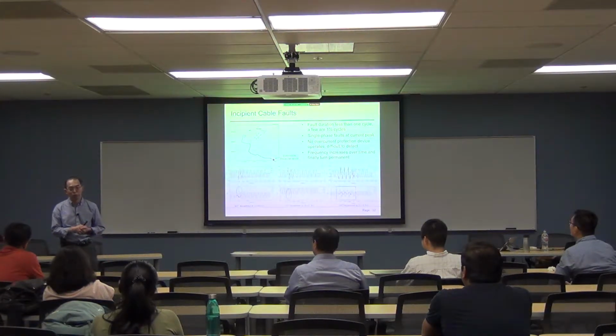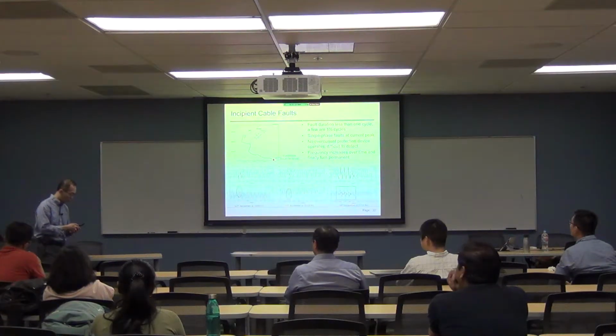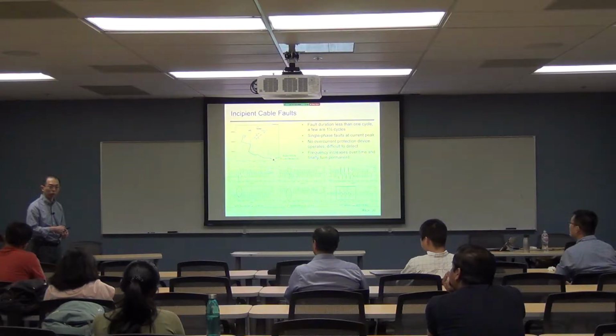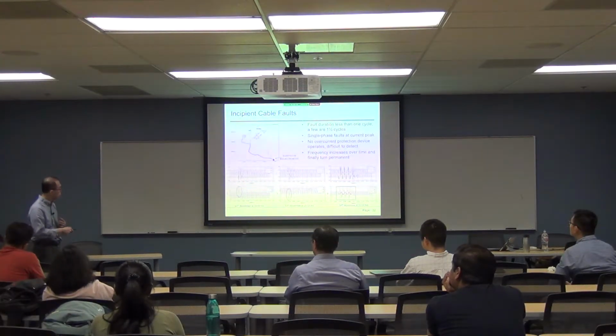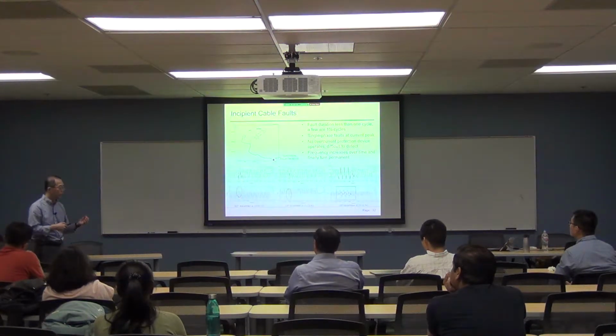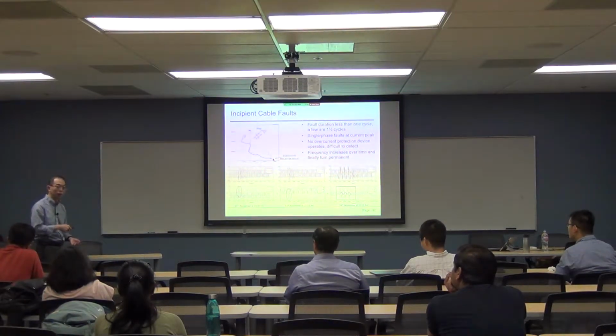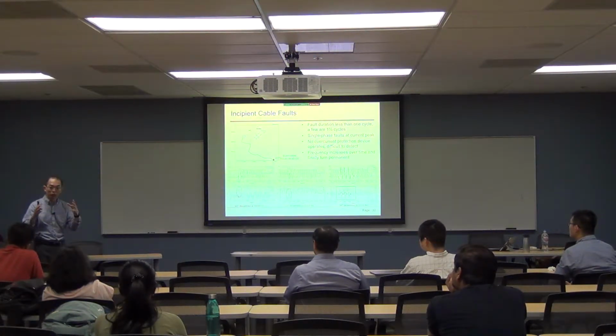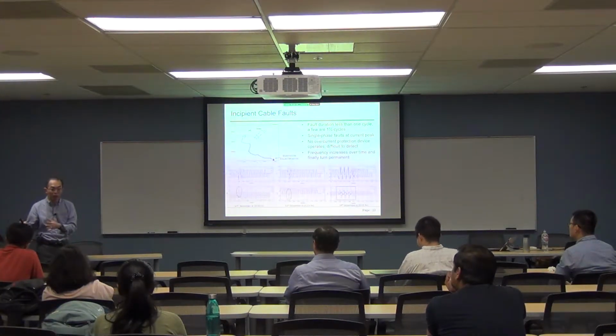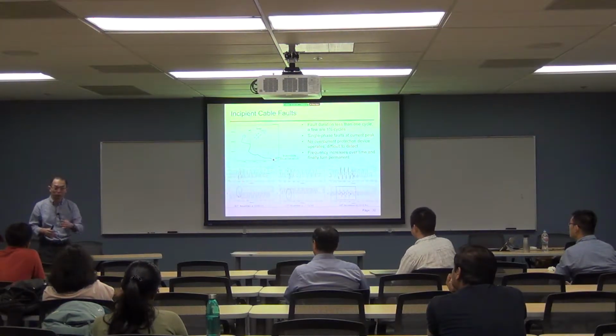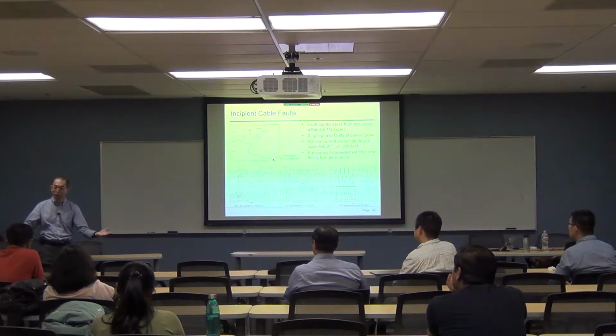But when you look at this waveform for the first time, you might be misled that the information to capture or identify the faults may be located in the voltage waveform. When you see that, it is not true, because actually the trigger, the root cause, is coming from the current. The current interacts with the impedance, giving rise to the voltage disturbance. That's what happens. So we need to know the phenomena. We need to know the theory, the circuit theory, how the disturbance happens. But if you're just looking at the waveform itself, you may end up in Chicago instead of in Tempe here, okay?